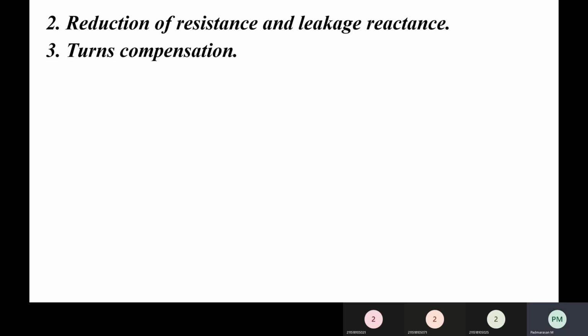So the remedy lies in making the K_T less than K_nom. This can be accomplished by either reducing the number of turns of primary winding or increasing the number of secondary winding turns. By doing so, it becomes possible to make the actual ratio K act equal to the K norm. That is, actual ratio is equal to the nominal ratio for one particular value of burden.